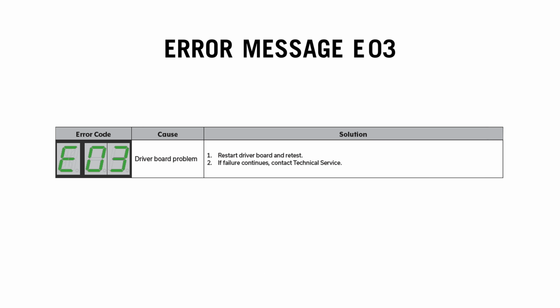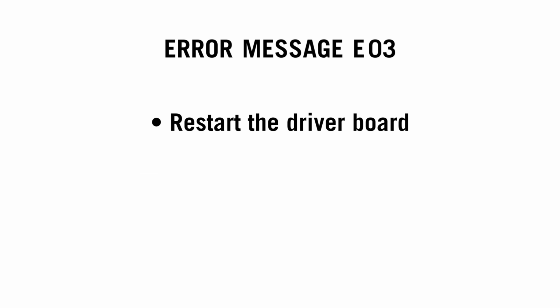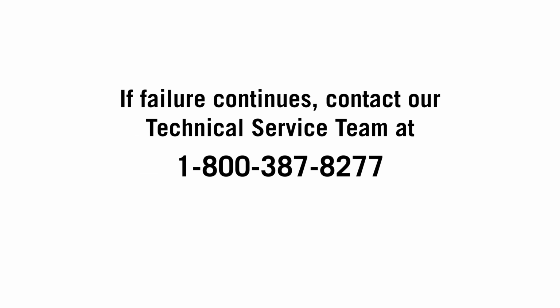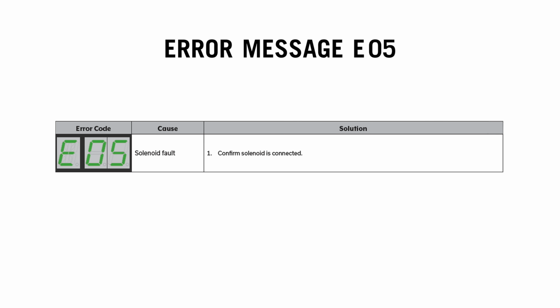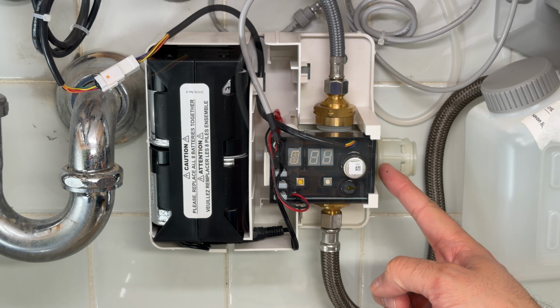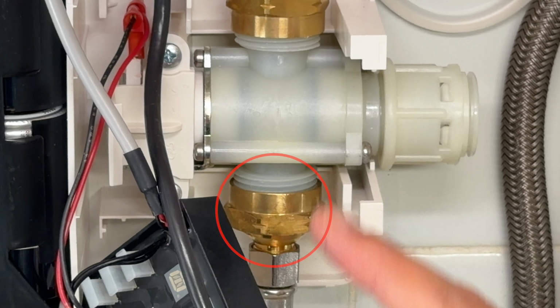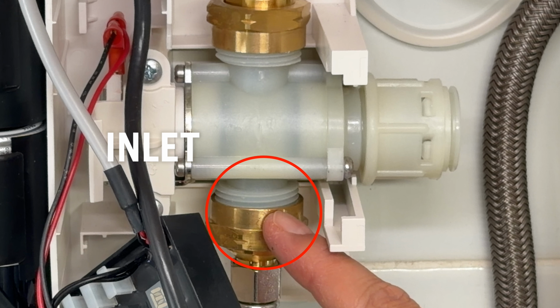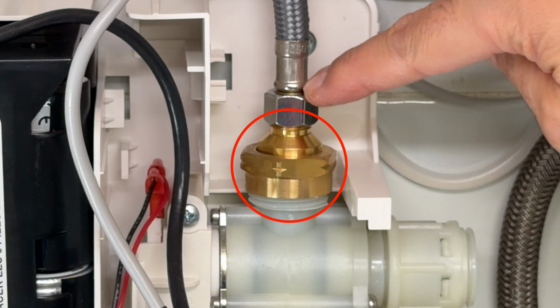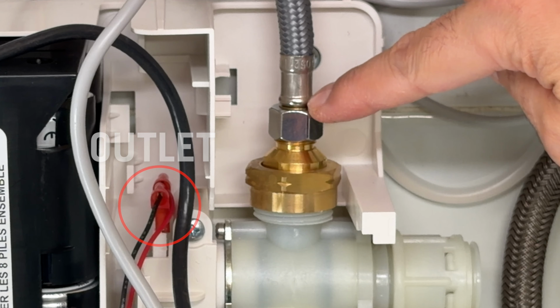If you encounter error message E03, this means that you have a driver board problem. Restart the driver board and retest it. If the failure continues, contact our technical service team. Error message E05 indicates a solenoid fault. Confirm that the solenoid is connected properly. If you confirm that the solenoid is connected properly and it's still not functioning, you might have a faulty solenoid. In this case, contact technical support for assistance.